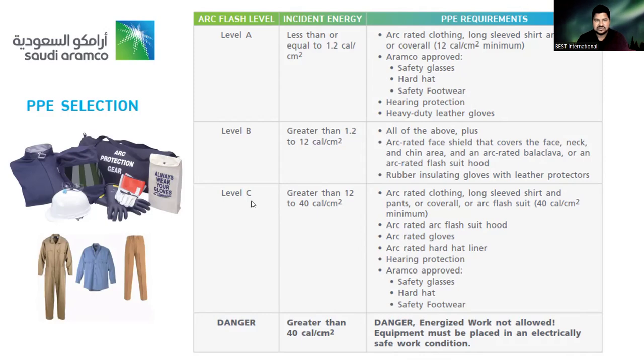Now, level C is greater than 12 to 40 calories per square centimeter. So we need arc rated clothing, long sleeve shirt and pants and coverall or arc flash suit, 40 calories per square centimeter minimum, arc rated arc flash suit hood, arc rated gloves, arc rated hard hat liner, hearing protection, and Aramco approved safety glasses, hard hat, and safety footwear.